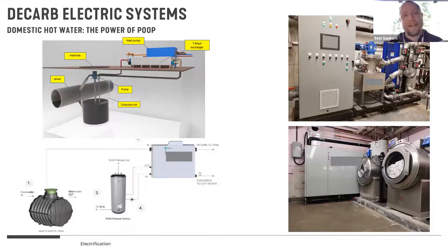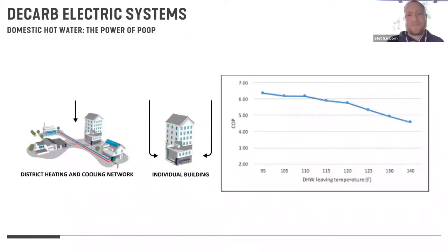And the really nice thing about this is the demand and the flow coming out of the building are happening at the same time. They're coincident. And so there's a ton of value in taking that source energy right at the time it's available, and then using that to create hot water and store it in tanks for use. And I'll show some sizing criteria in a little bit to walk you through what that scenario looks like.